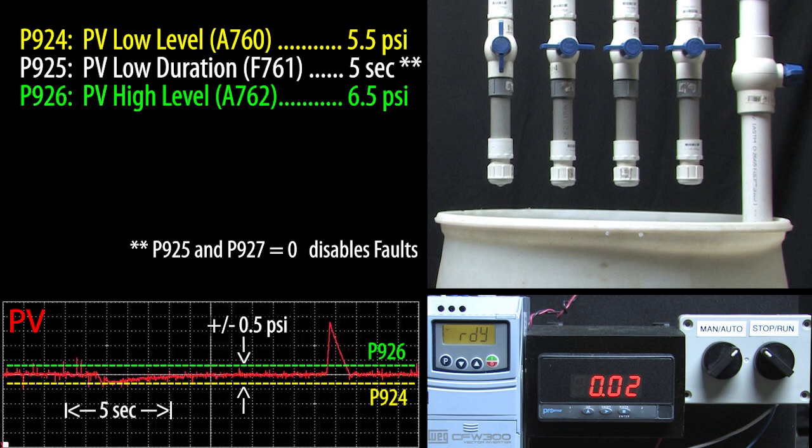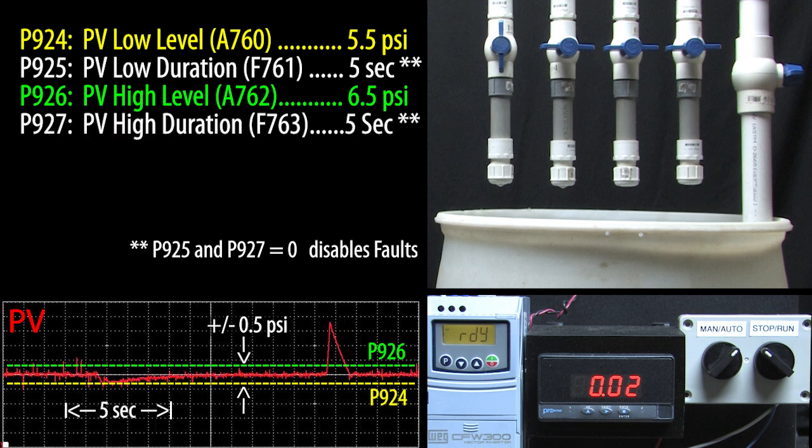Parameter 926 is the high side so we'll set that to 6.5 PSI. And parameter 927 is the duration of the high side. We want 5 seconds for that one too. It doesn't have to be the same as the low side. I just did that for this demo.